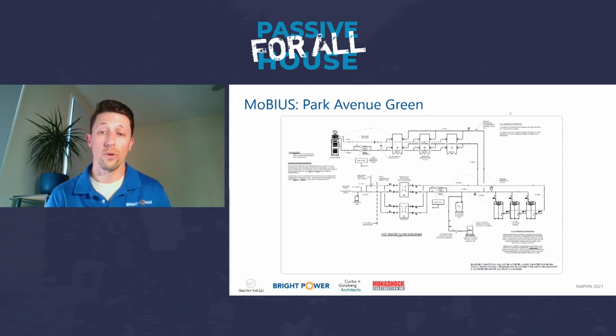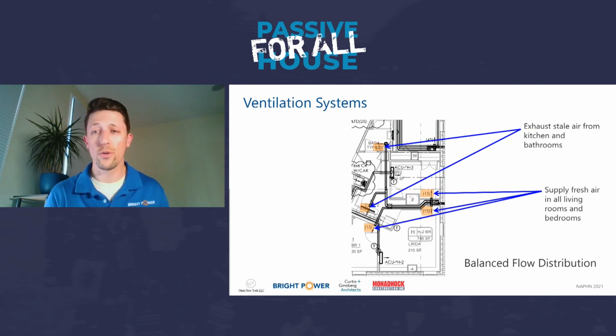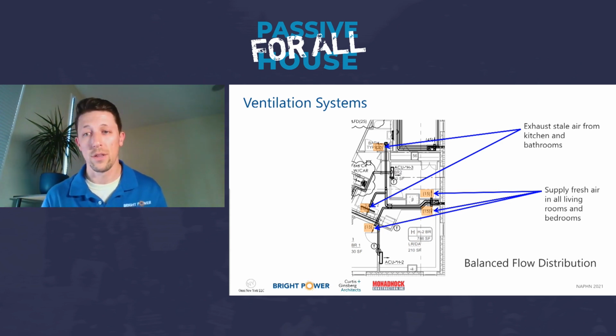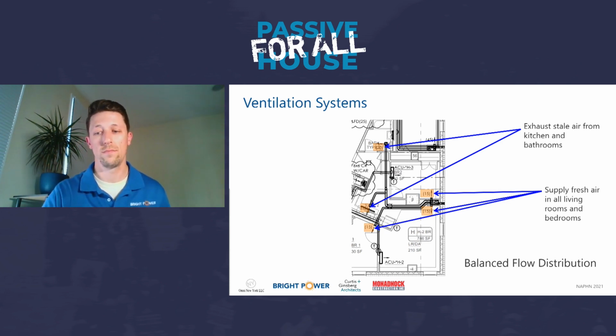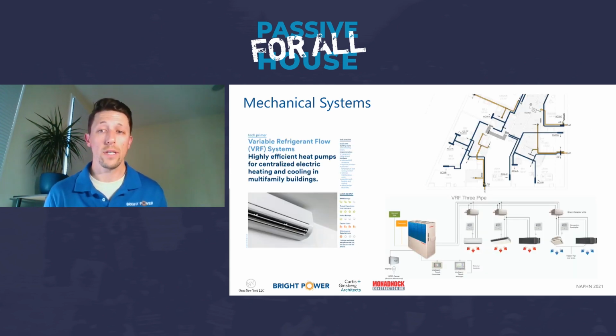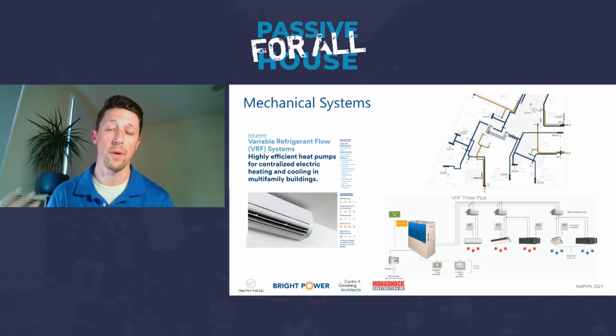Here's a quick look at the boiler room line diagram at Park Avenue Green, which is usually how we start identifying what equipment and points we want to bring into our monitoring platform. Park Avenue Green is equipped with unitized ERVs that provide balanced ventilation to all apartment units. There's also a much larger ERV on the roof that sends fresh air to, as well as exhausts the corridors. Heating and cooling is achieved through a Mitsubishi VRF system. We were able to integrate with the existing controls to extract apartment temperatures and usage data on the indoor and outdoor units. This will help us determine the efficiency of this system when paired with passive house construction.